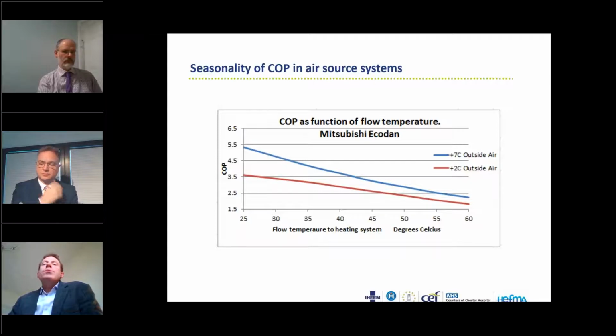In terms of air source heat pumps, our old-fashioned gas boiler is going to be about 85% efficient, or whatever the efficiency is. It will do that mostly throughout the year, whether it's cold outside or warm inside. It might vary a teeny tiny bit, but it's not going to vary very much. Whereas air source heat pumps are very susceptible to change in outside air temperature. So the COP might be 5 or so in the summer, when it's 15 or 16 or 20 degrees outside, but when it's -5 in the winter, it's probably not much better than an electrical resistance heater. So we need to think about how we integrate that type of technology into the systems we have right now.